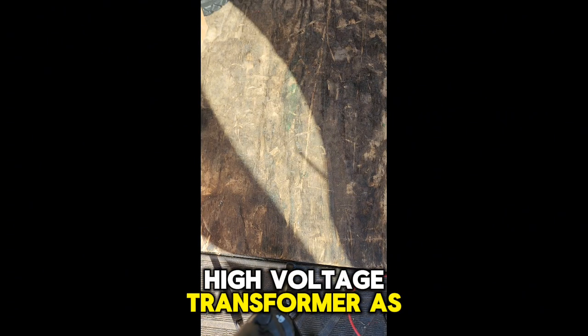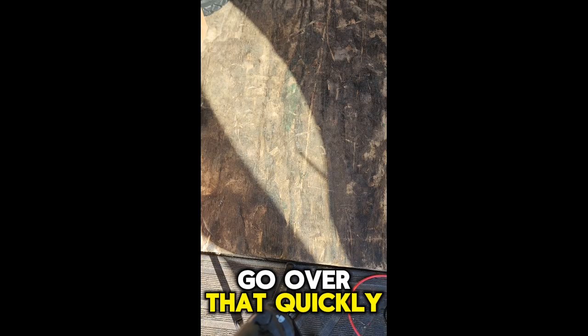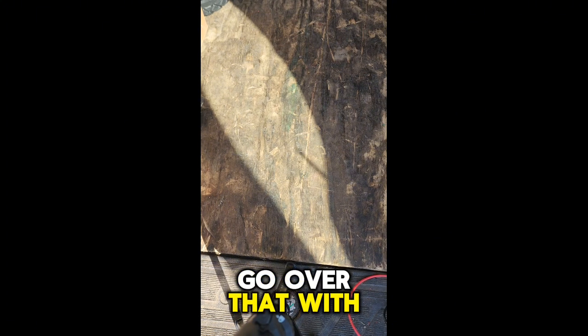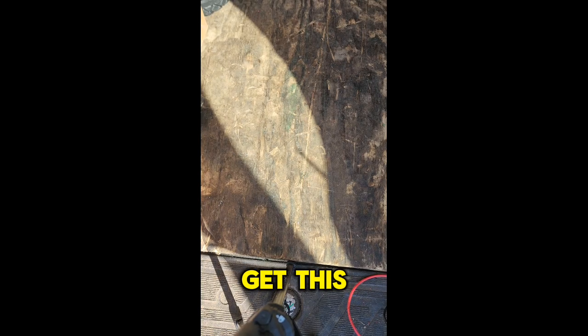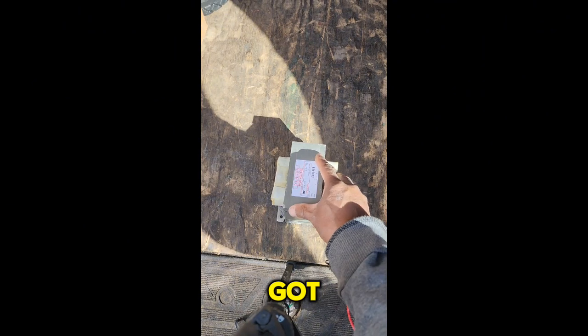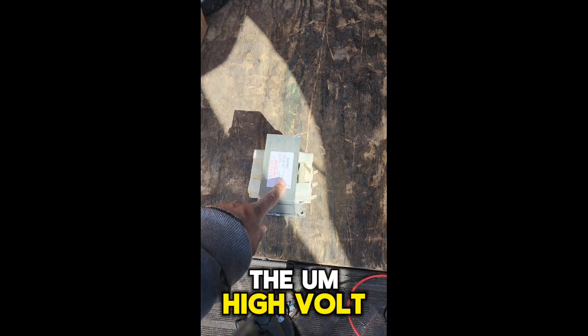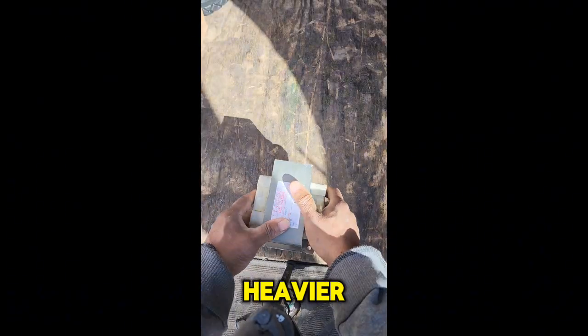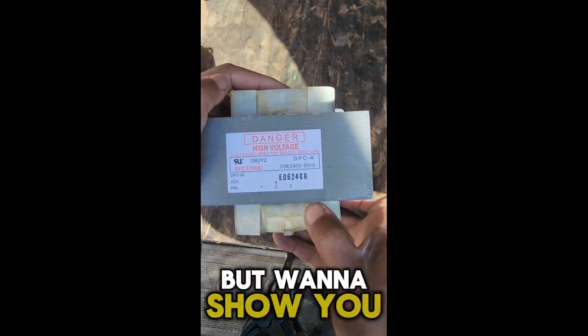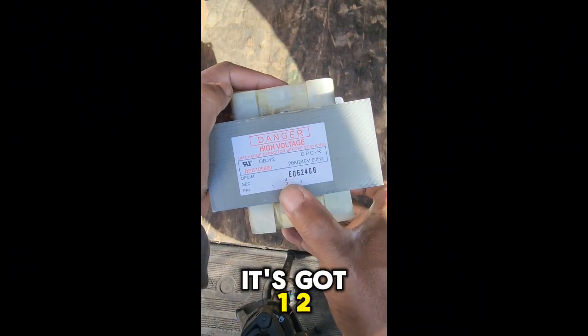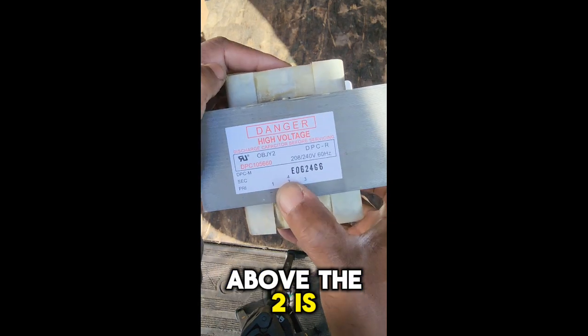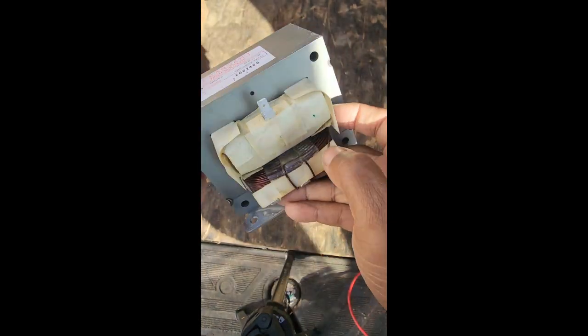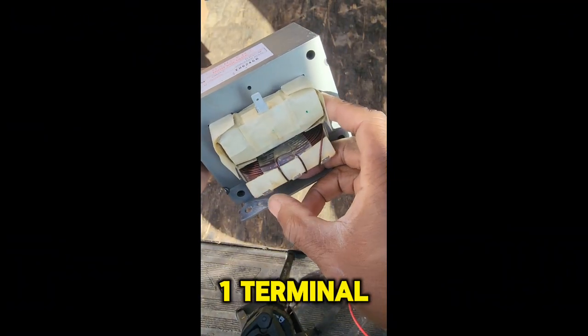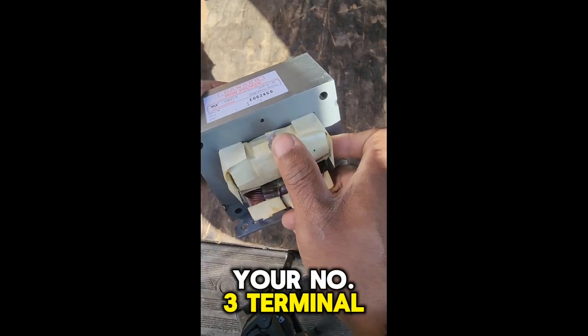And then I'm going to pull out the high voltage transformer as well, just to go over that quickly with you, because it does have a similar testing method, and I just want to go over that with you all. Just give me a second to get this back in its case here. So now we've got the high volt transformer. It's a lot heavier, so you just want to be careful with it, but I want to show you the numbering on it. It's got 1, 2, 3, and then just above the 2 is the number 4. This is your number 1 terminal, your number 2 terminal, your number 3 terminal, and this is your number 4 terminal.